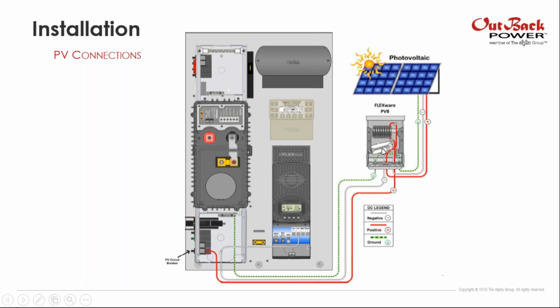In the case of the negative, we have a bus bar where you will join all the negative cables from the strings. For the output, you will have only one negative that is going to pass through the DC FLEXware, and you will connect it in the terminal that says PV negative in the charge controller. For the case of the grounding, it's very similar. Every OutBack device has its own terminal lug for grounding, so it will be very easy to identify it.